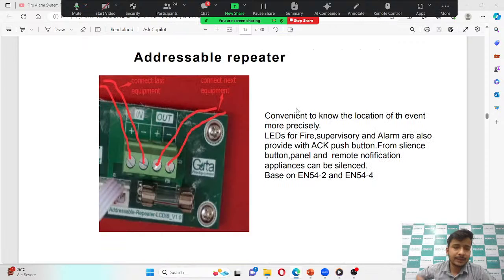Then our addressable repeater panel has simple connectivity like other devices, just loop in and loop out. Then it has LEDs for fire, supervisory, and alarm. And it has an acknowledge button and a silence button in case of alarm or any false alarm. So you can silence the remote devices or the main devices with the help of this repeater panel through this acknowledge and silence button.